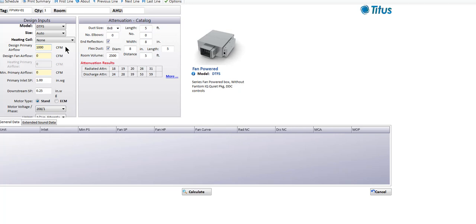We also get situations where people are looking for a fan-powered box that moves 5,000 CFM — that's basically a mini air handler. I typically don't like to see fan boxes handling much more than 2,000 CFM each. Once you start going over 2,000 CFM, you're creating a concentrated noise source above the ceiling, and that leads to other problems.